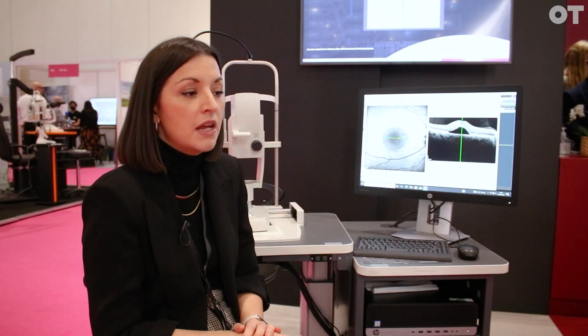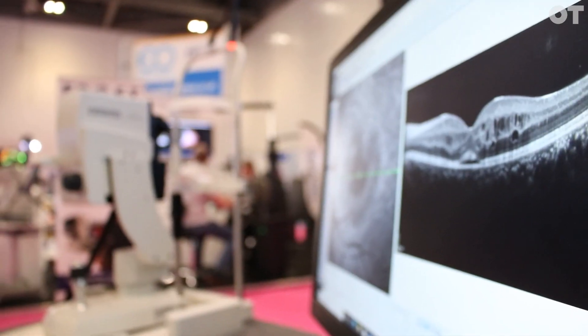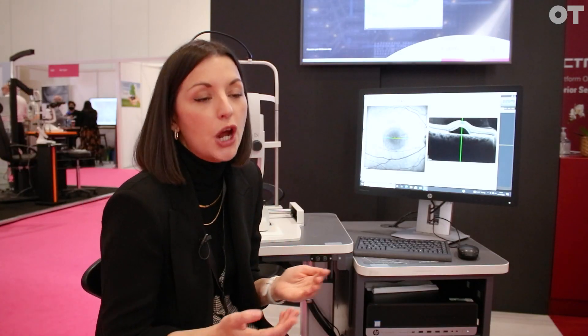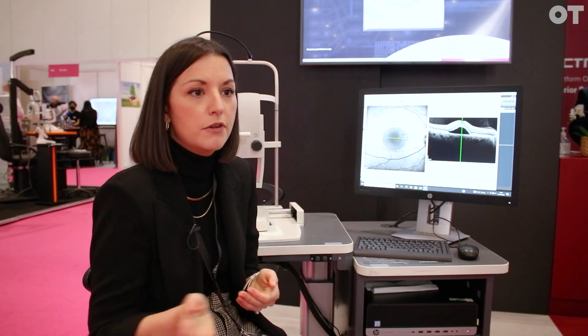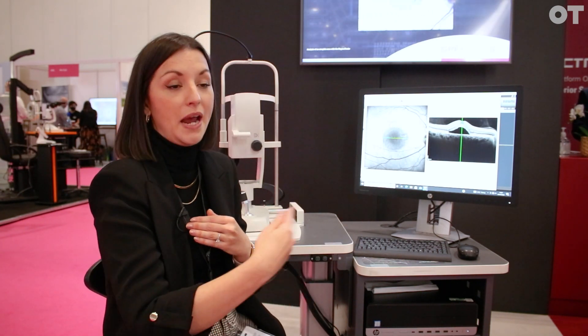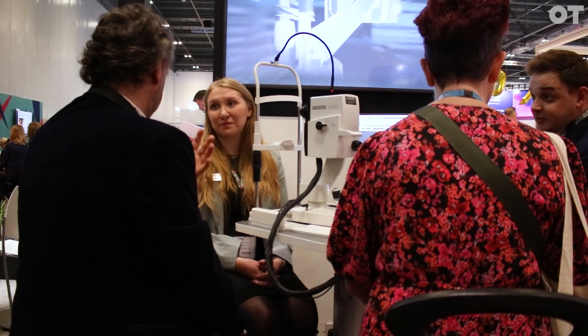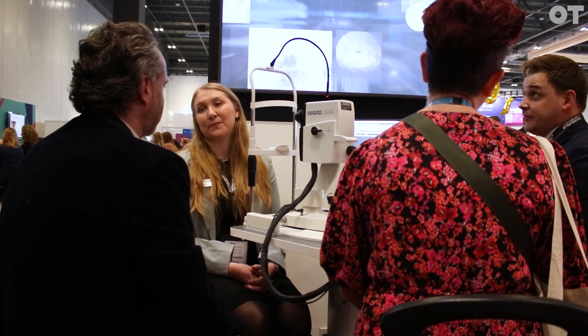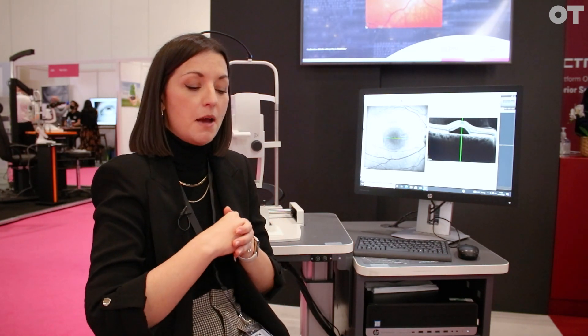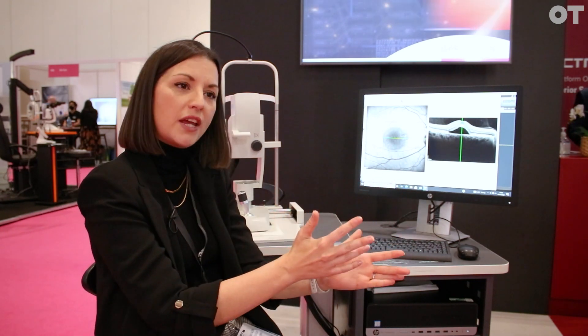Post-COVID, we've seen a huge amount of diagnostic hubs appearing and we've been very much involved in that — setting up diagnostic hubs for retina in Moorfields Eye Hospital, for example — to really deal with the COVID backlog in ophthalmology. These are one-way systems where patients come in, get all their diagnostic tests done in a kind of virtual clinic, and clinicians review at a later date. We've installed a lot of Spectralis and ANTERION platforms in these setups. They work really nicely because the two platforms connect together via our HEYEX software, which connects all our devices and even some third-party instruments — super popular in a diagnostic hub environment where you want everything in one platform.